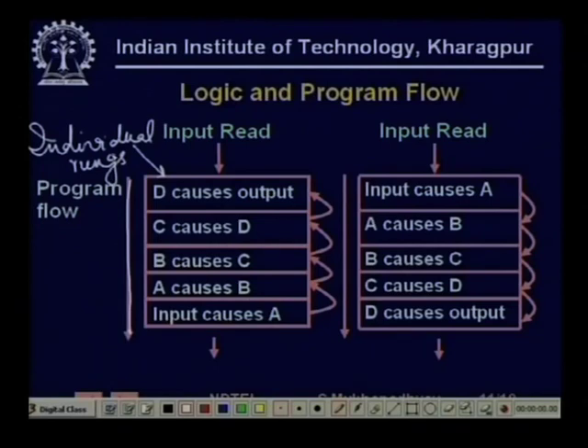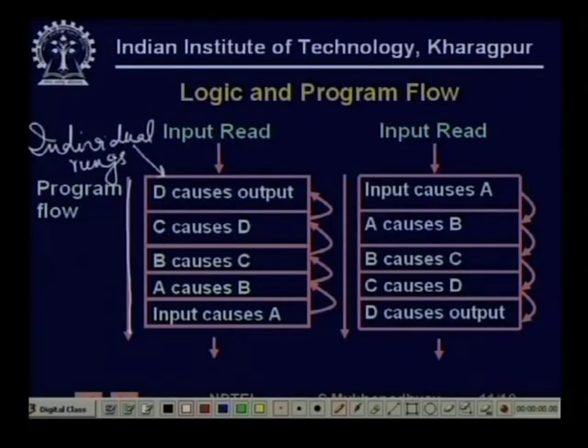Several logics are all executed between one input read and output write. It may appear that the order in which you put these logics is immaterial, but it does matter. For example, when there is a very complex logic you sometimes break it into several parts — you evaluate one small part, compute some value, then use that value in another expression and evaluate something else.